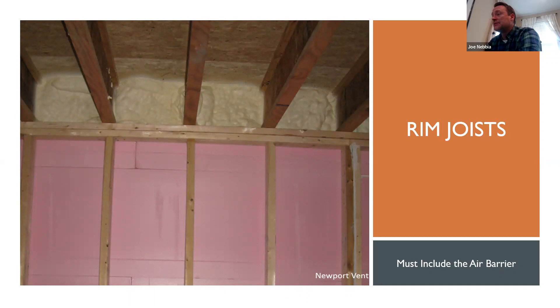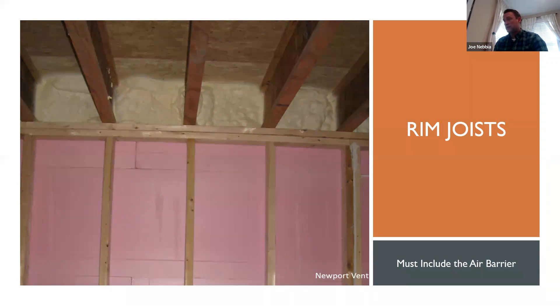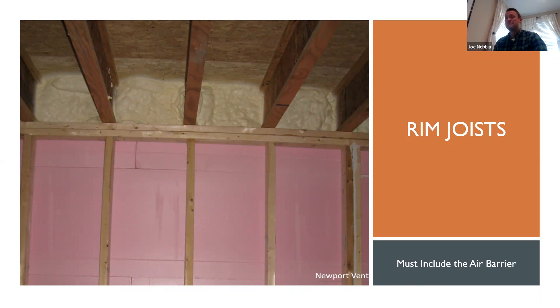Rim joists must be sealed. They must be insulated, and they must also include the air barrier. You can't skip the rim joists in the air barrier, even if you're in a floor over unconditioned space. Code says all rim joists must be part of the air barrier. Even if you're not insulating the basement below, you can't define your air barrier above that space. The rim joist has to be insulated and air sealed. If this was a floor over unconditioned space, you would see insulation there in the floor as well.